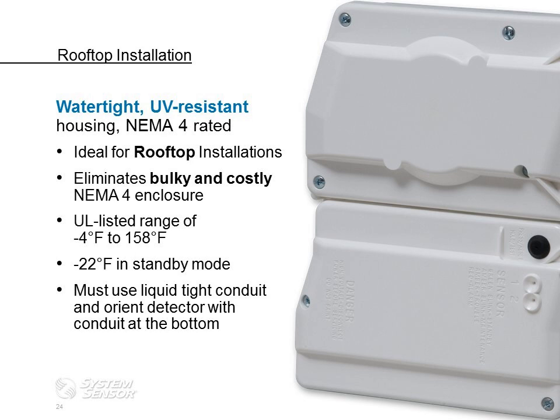One thing to remember about the NEMA 4 watertight version is you have to use liquid tight conduit and connectors for that installation. Using a non-watertight or non-liquid tight connector, basically on a watertight housing, is going to allow water to penetrate. So we have to use watertight connectors as well as the housing.